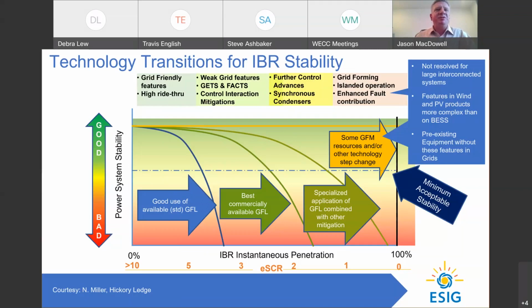systems. But in order to really get to integration of high penetration of inverter-based resources, with effective short circuit ratios approaching 1 and even less than 1, we need a transformation. We need a paradigm shift. One of the big aspects of the paradigm shift is the implementation of grid forming controls, allowing the stability to really manage a lot of the weak system issues that we experience in terms of control stability with grid following controls. So grid forming controls certainly help. They're not a silver bullet.